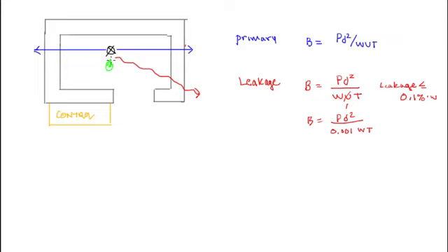Okay, now there's a third type of radiation. So you're radiating a patient, and radiation scatters off the patient and then comes through the barrier. So that's scatter radiation. The formula is complicated, so I'm not really going to get into it. But one of the principles in shielding is typically that in a linac, if you shield for leakage, then you're also usually okay for scatter shielding.